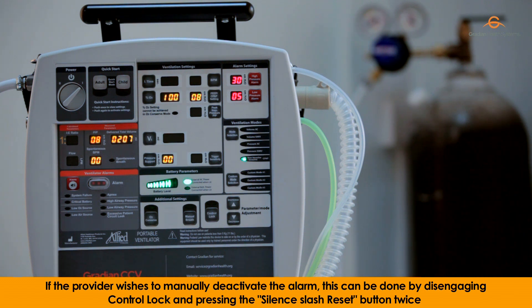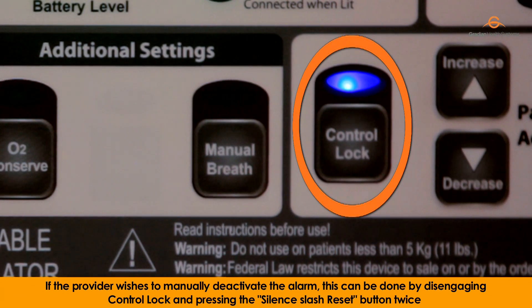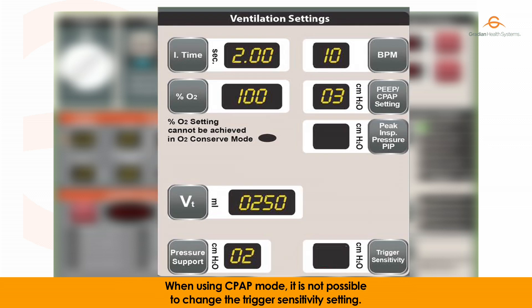If the provider wishes to manually deactivate the alarm, this can be done by disengaging control lock and pressing the Silence/Reset button twice, or by changing the ventilation mode or ventilation parameters. When using CPAP mode, it is not possible to change the trigger sensitivity setting.